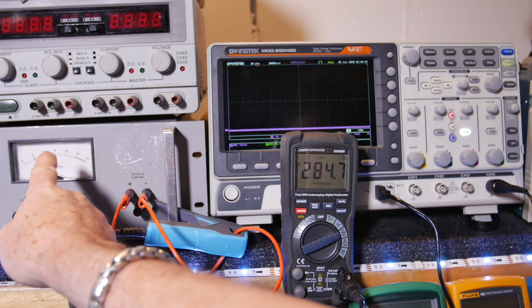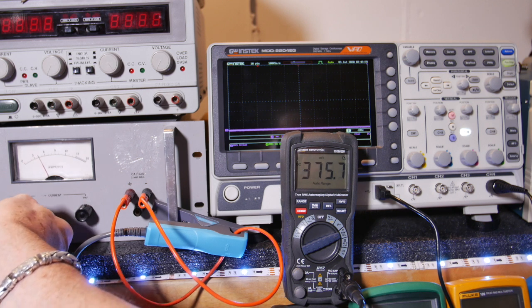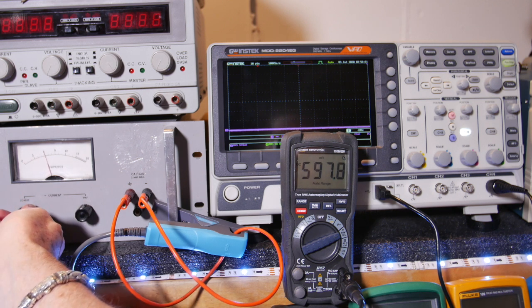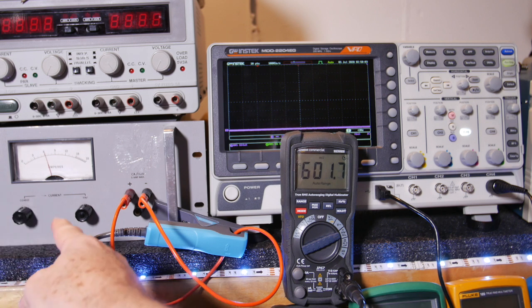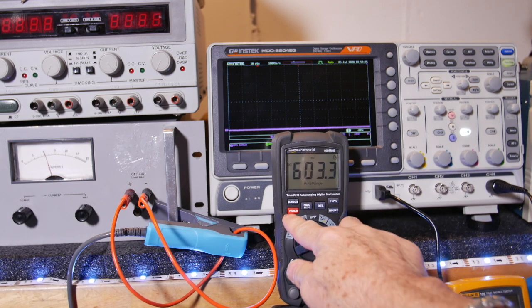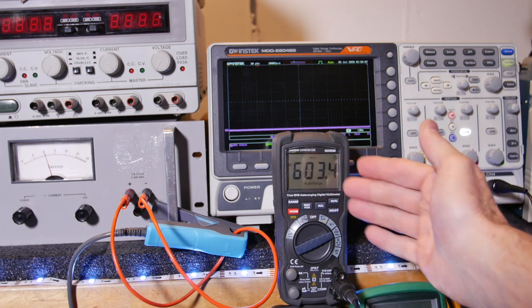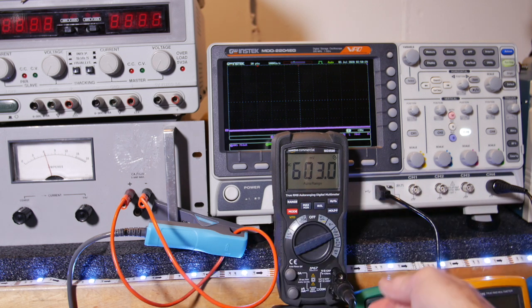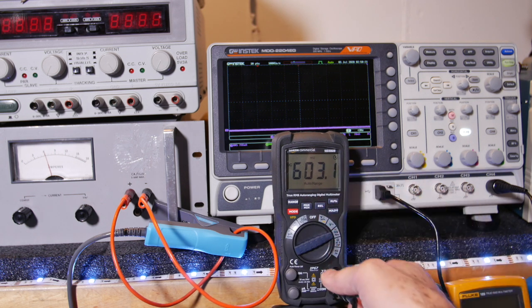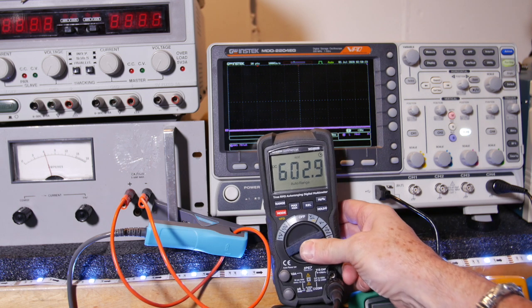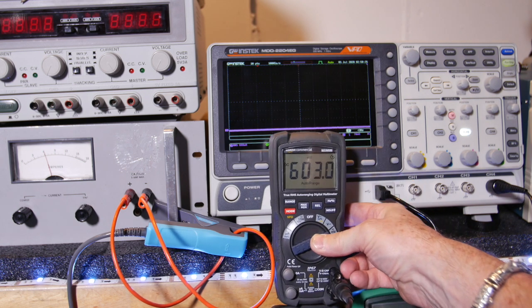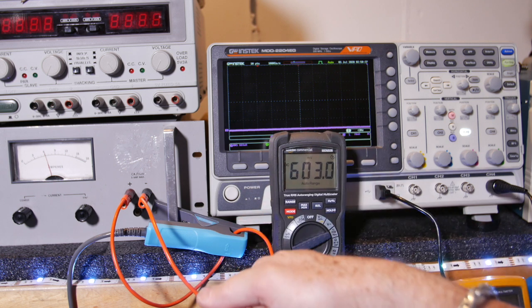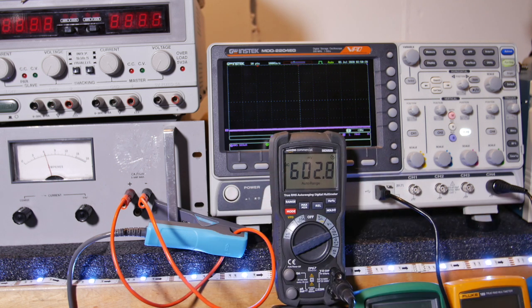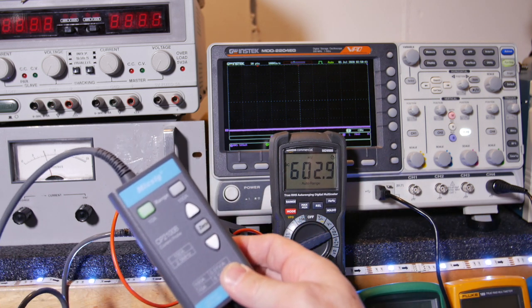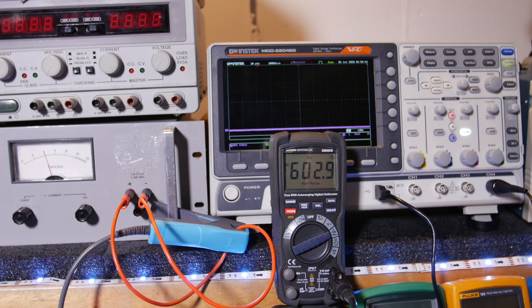Okay, now we know where the 6 amp setting is. It's just over the 6 amp. So yeah, it's right about there, and it says 600 millivolts, so it's really 6 amps. Alright, so yeah, you can use these things in a multimeter if you had a question about that. Stick in the millivolt range, and remember to multiply by 10 because of the times 10 sitting on your thing here, or times 100 for that matter, if you're in the 100 amp range.